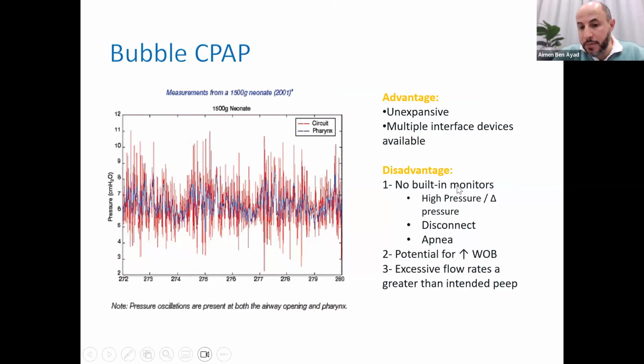A disadvantage of bubble CPAP, unfortunately, because it's simple, is that it doesn't have a built-in monitor. So what I'm trying to say is, if the interface disconnects from the baby, there is no way to know it's disconnected unless the baby starts desatting, or you are close enough to the baby that you can see the machine is not bubbling, or the expiratory limb is not bubbling inside the bottle or can of water. So that's a very important connection. The nurse has to be close to the baby so she can see the bubbling. Or you wait until the baby starts desatting, which is not a good practice.